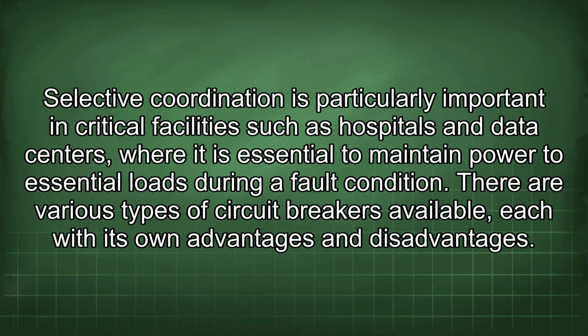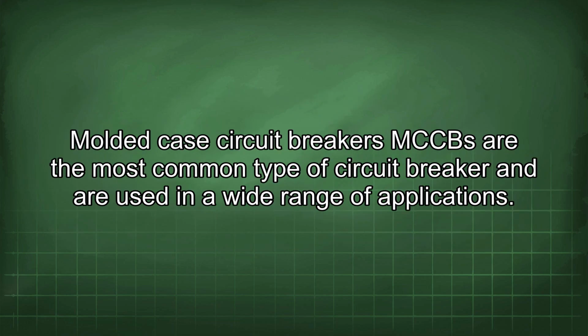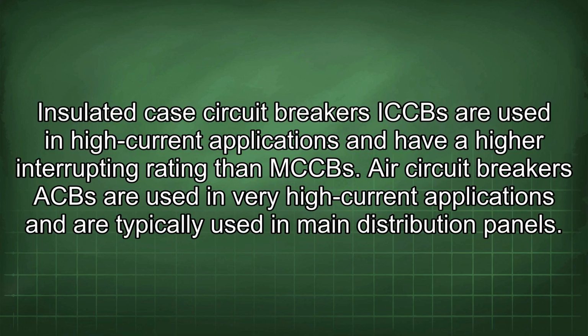Selective coordination is particularly important in critical facilities such as hospitals and data centers, where it is essential to maintain power to essential loads during a fault condition. There are various types of circuit breakers available, each with its own advantages and disadvantages. Molded case circuit breakers, MCCBs, are the most common type of circuit breaker and are used in a wide range of applications. Insulated case circuit breakers, ICCBs, are used in high current applications and have a higher interrupting rating than MCCBs. Air circuit breakers, ACBs, are used in very high current applications and are typically used in main distribution panels.